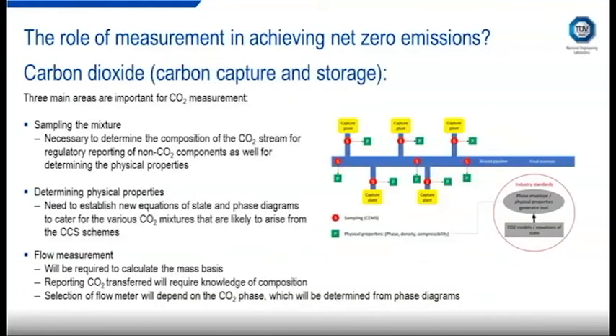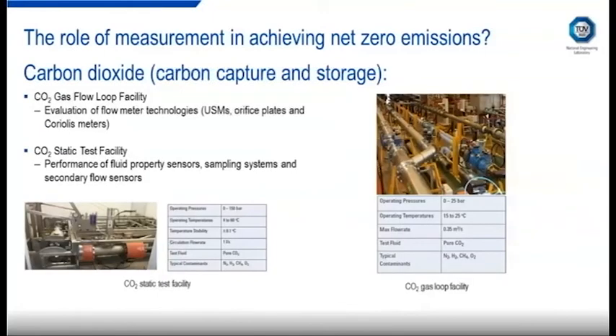So as we see it, there are various challenges in terms of accurate CO2 measurement and CCS mixtures measurement. There needs to be accurate sampling, so you know exactly what is in the mixture. There needs to be a greater understanding of the phase behavior for these mixtures, so that includes development of new equations. And the flow measurement as well has to be accurately specified. Depending on the conditions, you could have CO2 in the gas phase or in the liquid phase. This is going to affect the meter selection that you make. And it's going to be especially challenging if you can encounter two-phase flow conditions, because most flow meters are not well suited for those conditions. So it's a very challenging area, and the exact technical solution to it depends largely on the operating conditions, which are not that well detailed at the moment. But regardless of this, we've done some work in this area already.